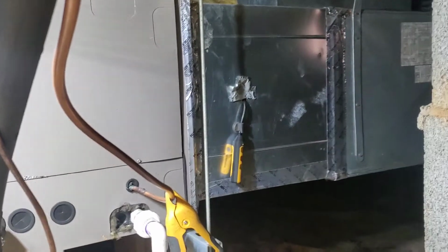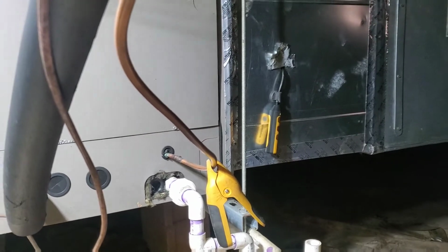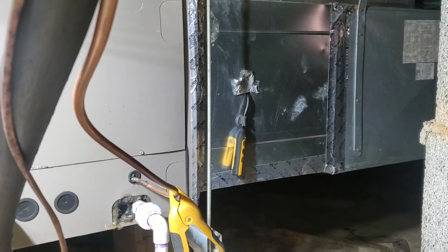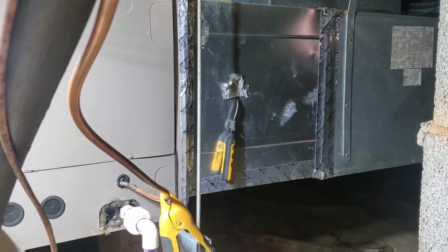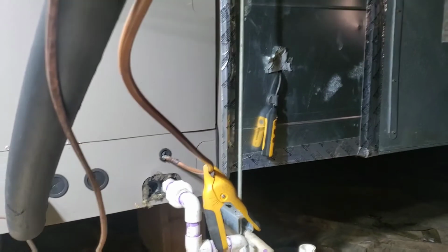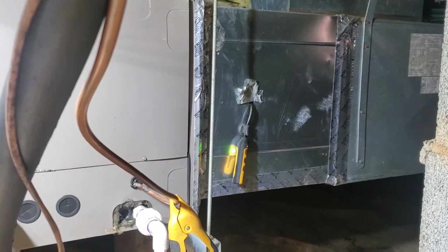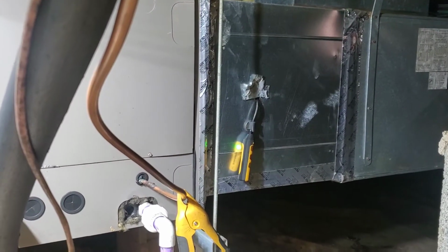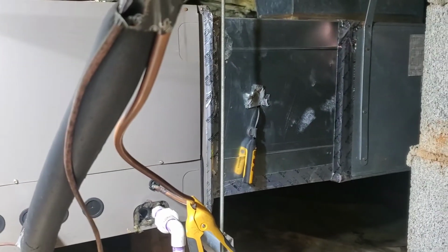But when it's overcharged, think about what happens. This warm liquid refrigerant comes out of our indoor coil and it eventually sits there waiting to be used by the outdoor TXV. Well, if you're overcharged, you've got all this liquid that's stacking up in your indoor coil and it's not being used. So it's just sitting there getting cooled down and cooled down and cooled down by your return air. So your approach will also be low if you're overcharged.